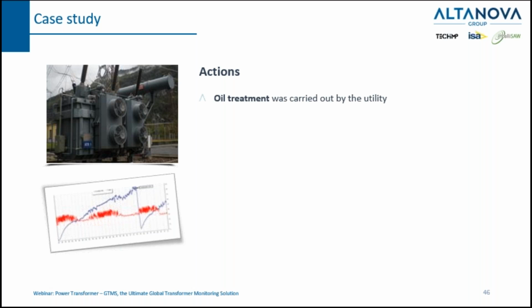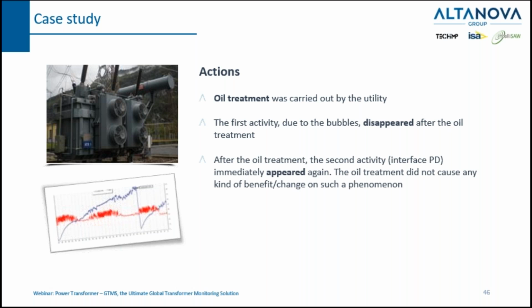After this first period, the utility decided to perform an oil treatment, which was carried out in a couple of days. The first activity we recorded, the PD in bubbles, disappeared after this treatment. And the second one, the interface PD, immediately appeared again. So in this case, the oil treatment did not bring any benefit in reducing this kind of phenomenon.